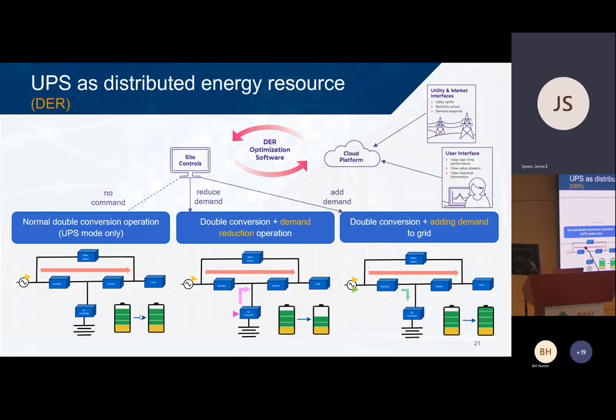And the battery capacity is basically held available, all of the battery capacity, to support the critical load. But if you look at the battery icons just below the graphic, you notice there's a yellow segment at the bottom, and that is the amount of battery capacity that's needed to keep that data center running for, let's say, 7 minutes. So what's all the green stuff up above? That's unused battery capacity. And the white area right above that, if you can see my cursor, is excess battery that has not been charged. So this battery is probably sitting at 80 or 90% charge instead of 100%.